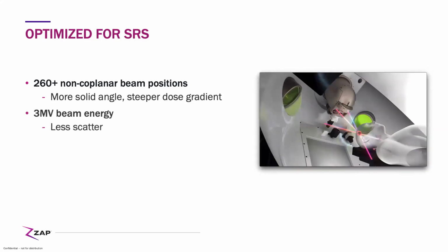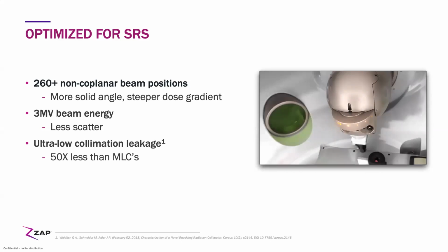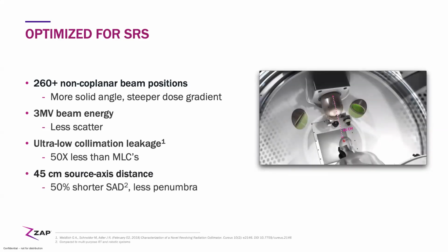3 MV beam energy gives you less lateral scatter, again giving you better dosimetry. The collimation system, which we'll show in a little more detail, does an amazing job of stopping almost all scatter off the primary target. And so all you're dealing with is just a tightly collimated beam of radiation emitted through this cylindrical collimation system. Far less scatter radiation than occurs with your standard multi-leaf collimator. In fact, 50 times less. And then lastly, this runs at a 45 centimeter SAD. Shorter SAD, significantly less penumbra. So more solid angle, beam optimized for brain radiosurgery, better collimation, shorter SAD.